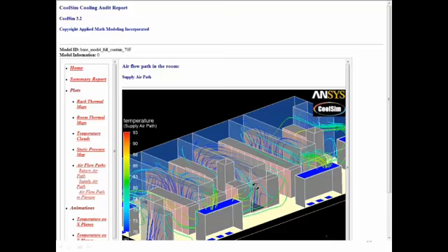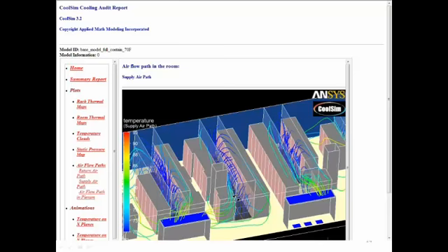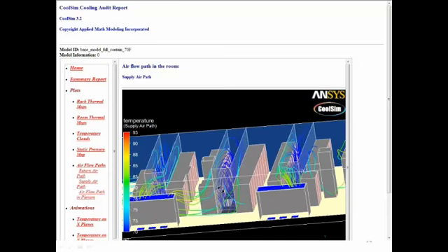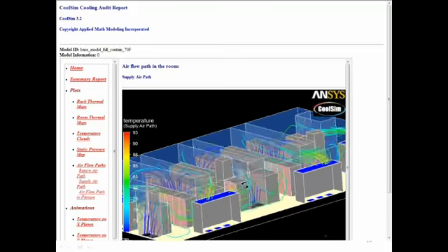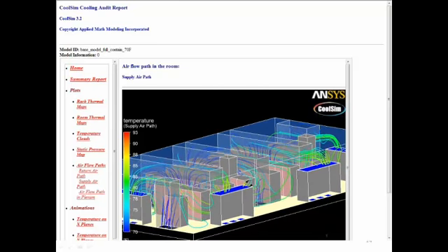So you can see here that, of course, it's leaking much less. We do have a little leakage going on here, of course, because A, curtains do leak, all barriers do leak, and B, my supply is greater than my requirement through those racks, and so you've got to account for the excess. The excess mass flow has to get back somewhere, right?